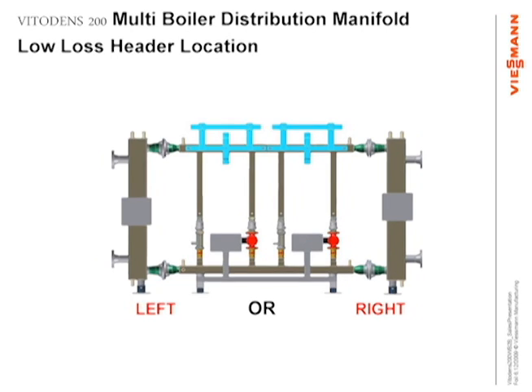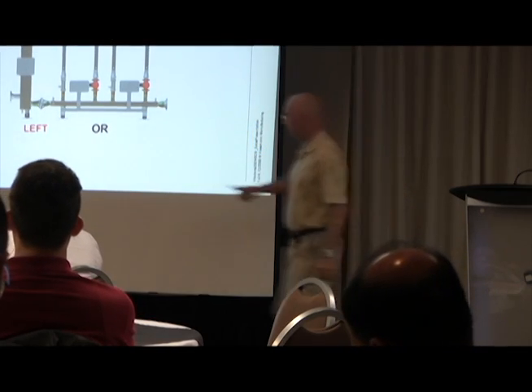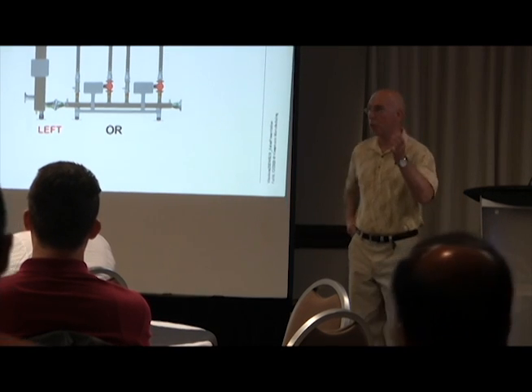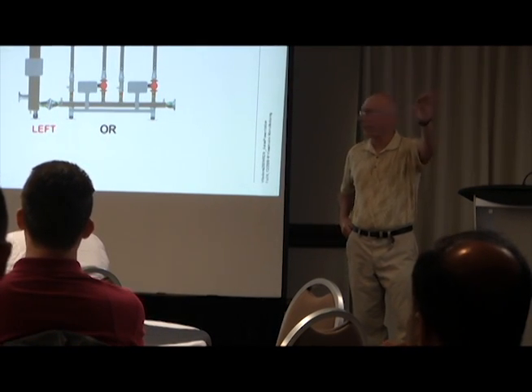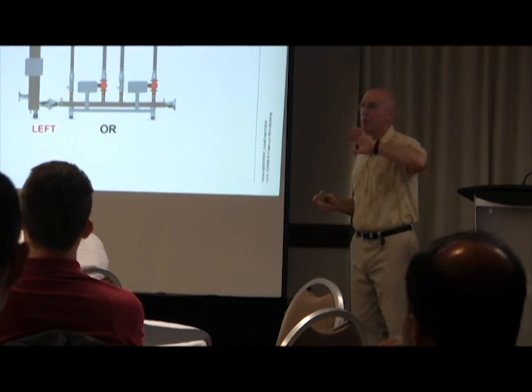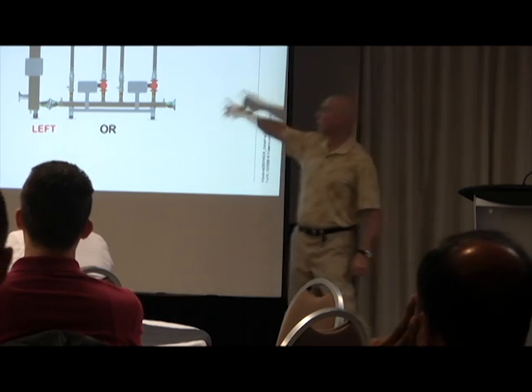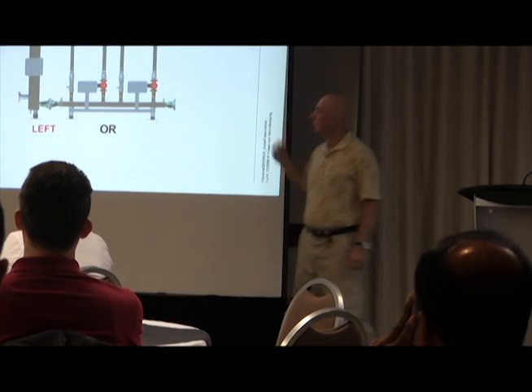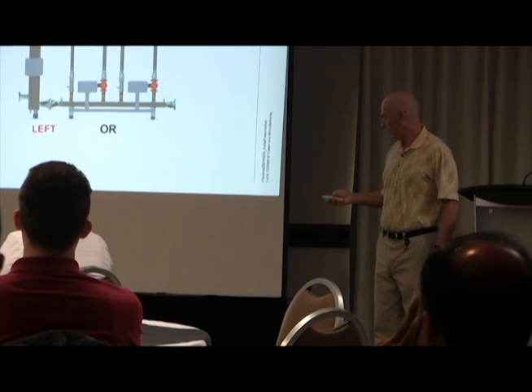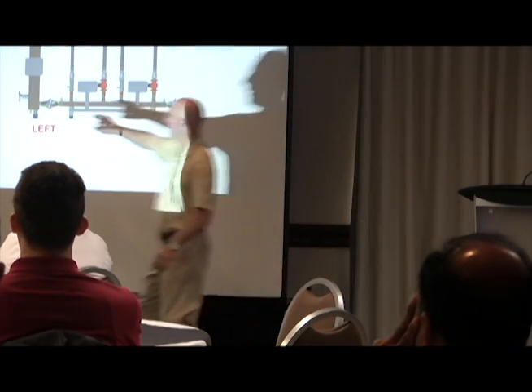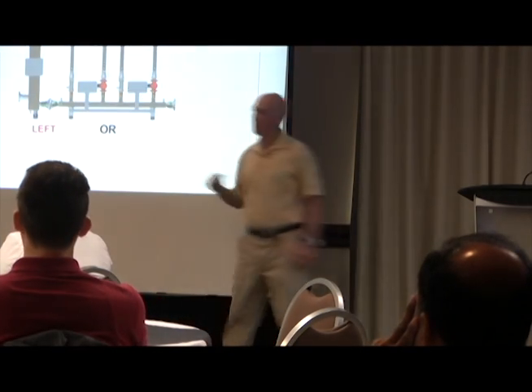This is the 2 boiler manifold setup. We also have an item called a low loss header - probably one of the handiest pieces of equipment we have right now, especially for retrofit applications. If you don't know what the flow rates are in the building, you can put on a low loss header, which is basically a system decoupler that allows you to put a larger size pump on the system without exceeding your flow rates on the boiler side. Basically it's an empty chamber where you'd have your pumping over here for your system, and your boiler pumps in here, so that you don't exceed the flow rates.